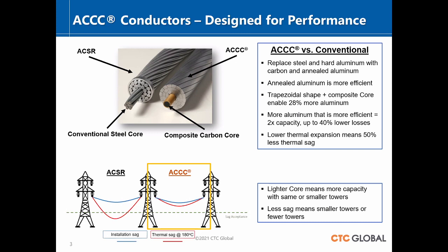Future proofing is something we hear in a number of applications in some of the markets of the world. We'll touch on that. But by putting this up and getting the benefit of that overpower, you can draw more power. You've got energy savings and carbon reduction potential immediately available, but it's also cheap insurance for planning model risks, under forecasting in some markets. It's not something we've experienced in a decade or so. We've been seeing a different kind of risk, but this allows you to change the flow on the network, something you may not have planned for, or an upset in the network, and still be able to continue to operate, because you can put 2 times the flow through these lines and they'll stay in service.